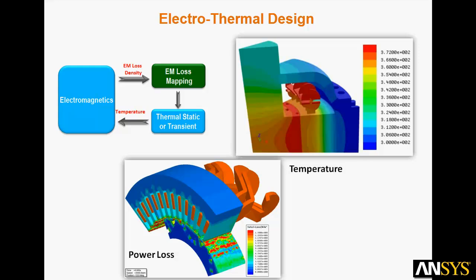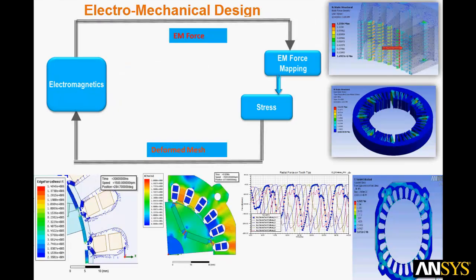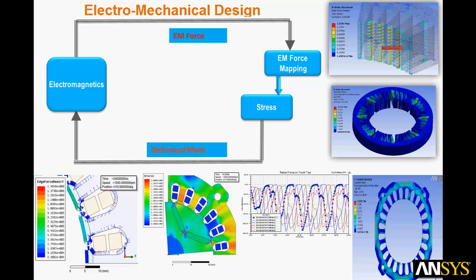The next step is electromechanical design. In this case we map the electromechanically induced forces to a finite element stress analysis in ANSYS mechanical. Again, automated procedures in ANSYS workbench streamline the process. The mechanical stresses deform the geometry and the deformed mesh information can be passed back to Maxwell for further electromagnetic simulation.